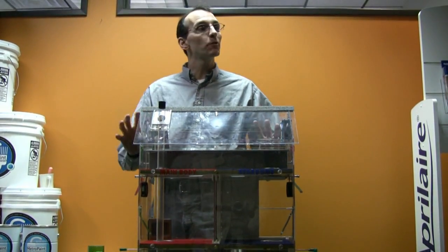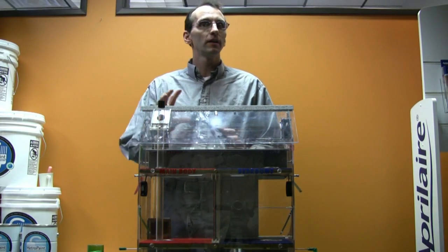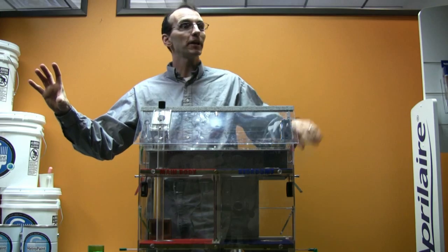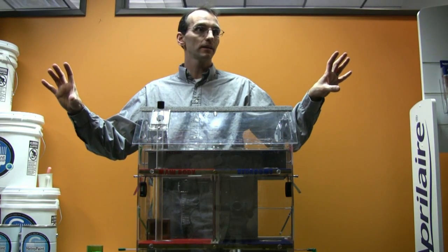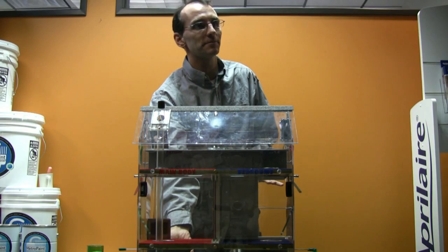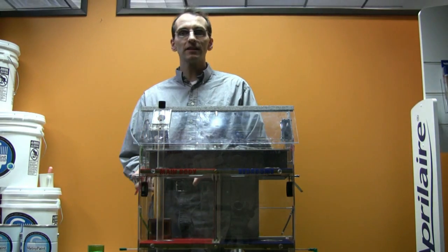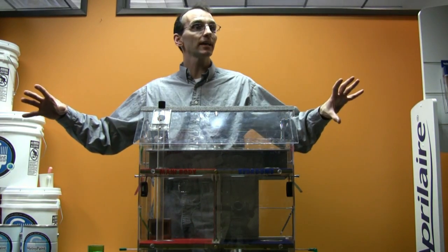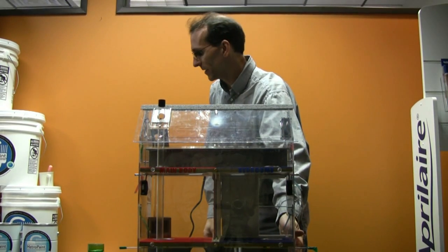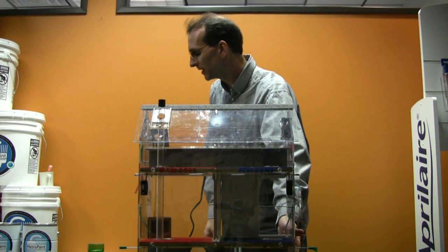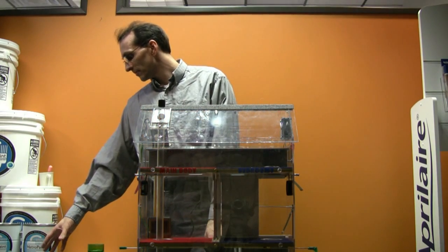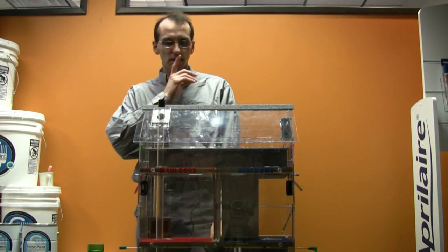But what will really make that worse is if the ductwork is leaky on the return side but not leaky on the supply side. Because the ductwork is down here in the basement, if it's leaky on the return side, it's going to act like an exhaust fan and suck air out of that area. So if I make it tight on the supply side and leaky on the return side, I get even a little more negative, minus 1.5.